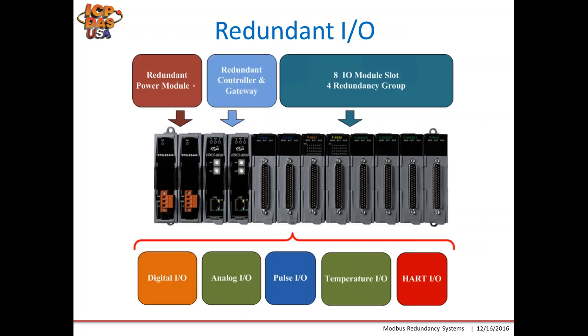This picture shows a close-up of our IDCS remote IO system where it has redundant power modules and the ability to add up to eight IO slot modules. You can either have pairs where they're the same IO type and have multiple connections to the same sensors and end devices to provide IO redundancy, or you can have one of each type of module and still have redundant power and redundant communication without IO redundancy.